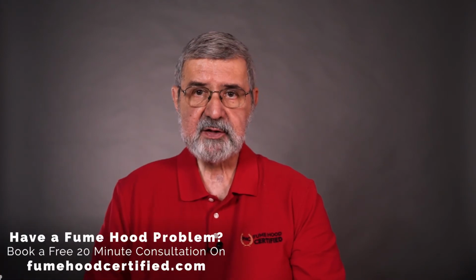Today, most labs have VAV or variable air volume controls. Remember, for your hood to function safely, the room has to stay balanced. That means that the room remains slightly negative to the hallway, and the amount of supply air at any given time is roughly equal to the amount of air the fume hood is exhausting. So we have both exhaust and supply volumes to manage.